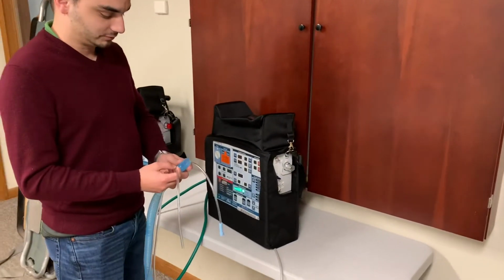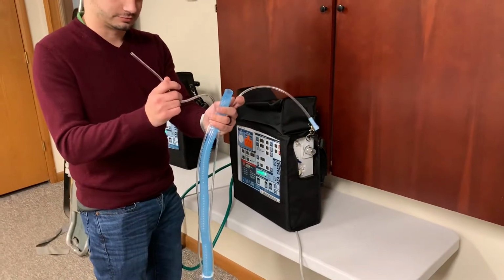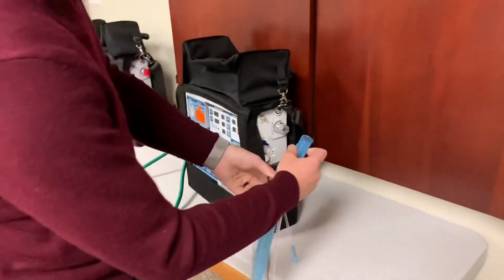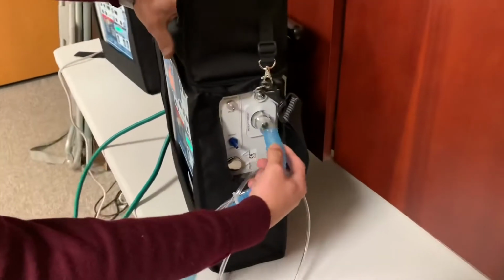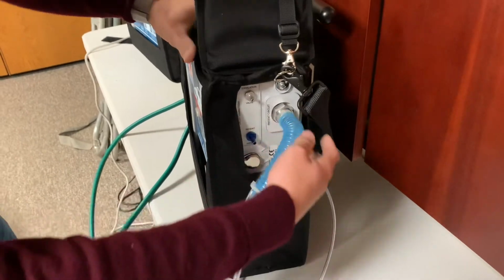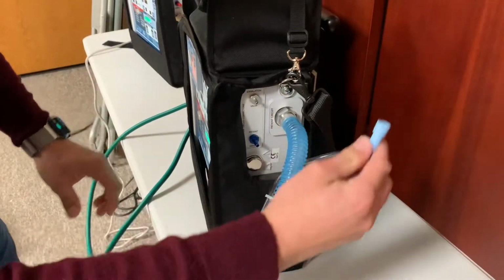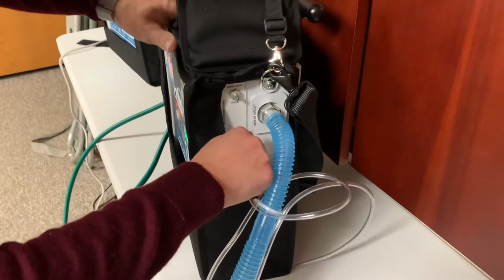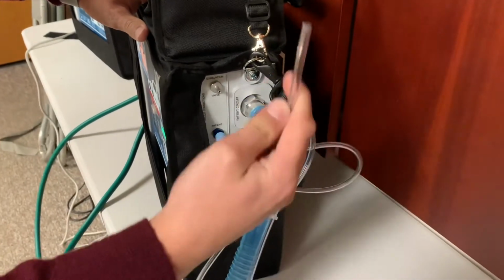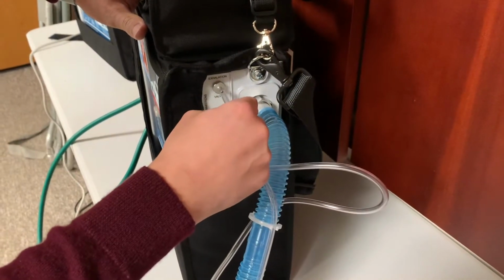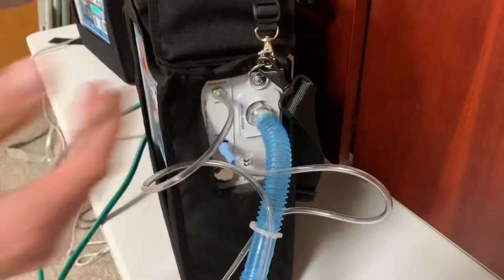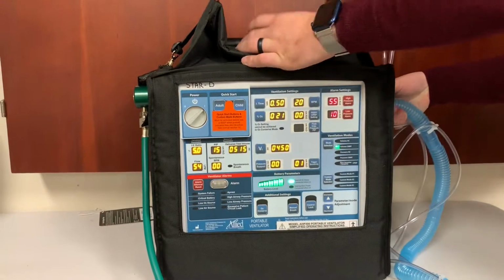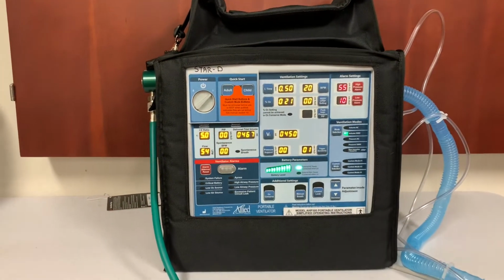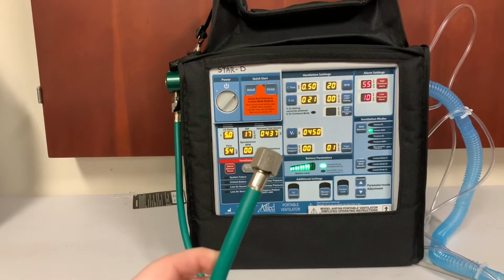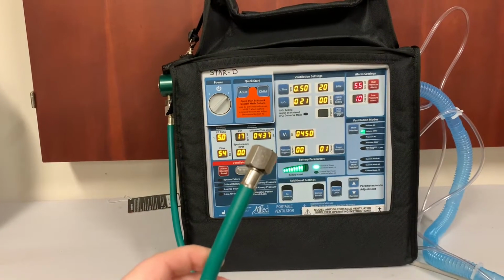First, we'll start by connecting the ventilator circuit that comes straight out of the package to the ventilator device. There are 3 tubes. They will only fit in their proper spots, including one being color coordinated. Blue goes to blue. Now that you have your circuit connected, you'll also, of course, want to make sure that your oxygen is connected to either your S valve on your portable tank or on your onboard regulator.